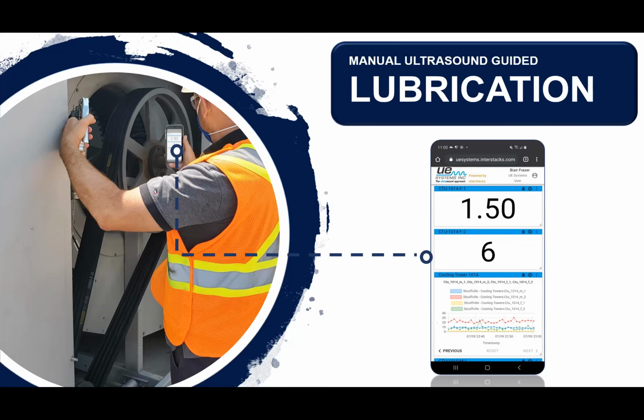But the challenge we got, and this is a good example, is that as most of you know, when you lubricate a bearing, you need it to be spinning. This happens to be a cooling tower - many of you have cooling towers and are starting to think, yep. What did you have to do if you had to bring those lubrication lines outside of the cooling tower so you don't get your head chopped off while lubricating? Or you went to these automatic lubrication devices.